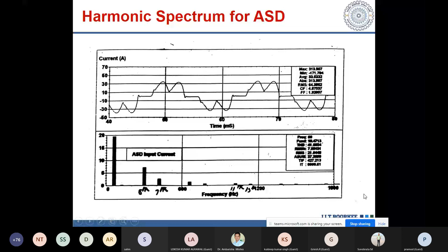If the speed of the machine is different, then you may have current like this, or like this. They have different harmonic spectrum. Like in this case, if it is operating at rated speed, you have third harmonic of this magnitude, fifth harmonic is quite large, then seventh, like this. But if the machine is running, this is one particular application, at 42% speed, then third is very small, fifth is very small, seventh is also small. So you cannot say that if the machine is running under rated condition, the harmonic spectrum will be good. It depends on so many other things.